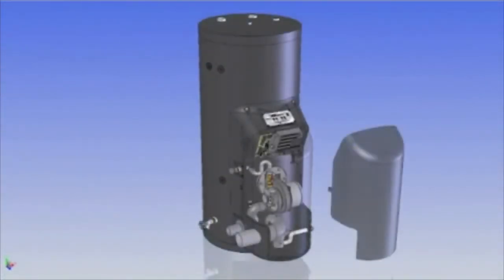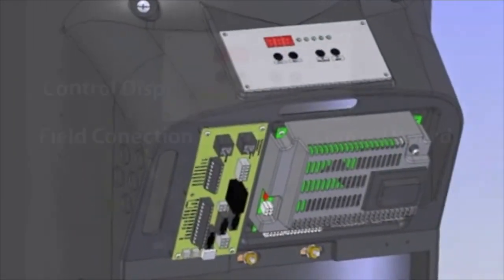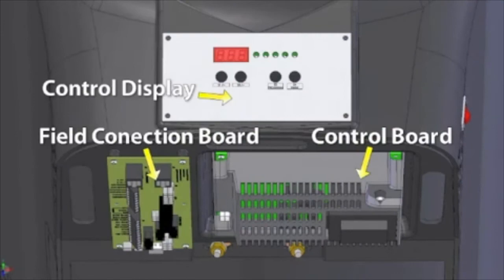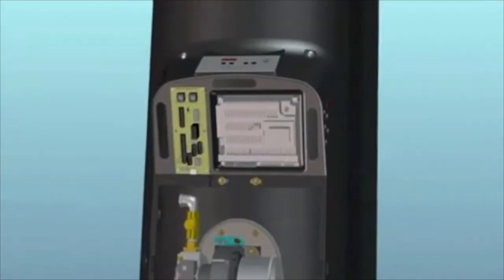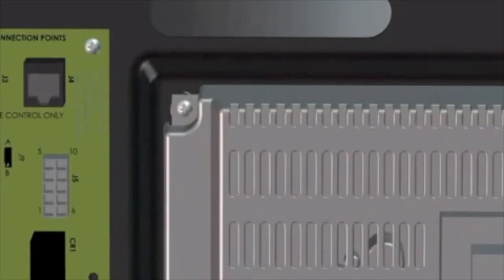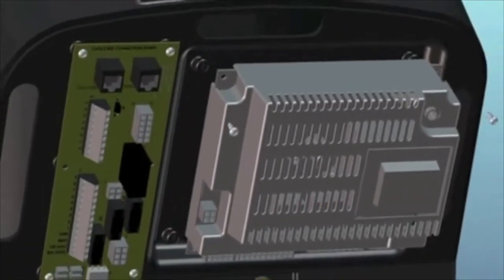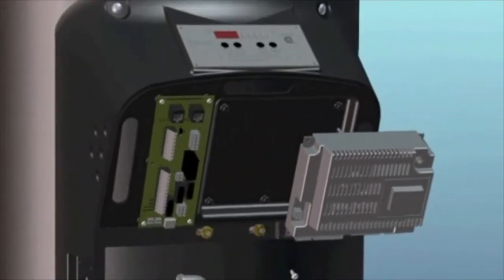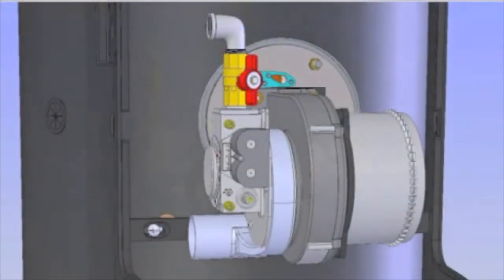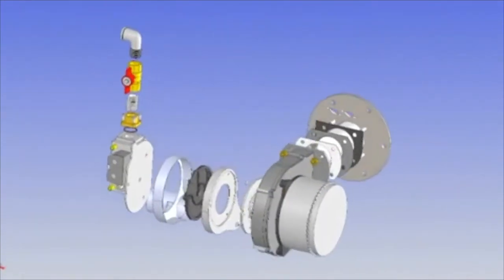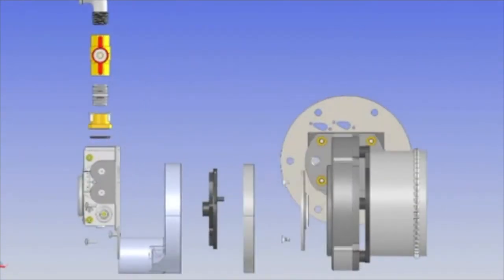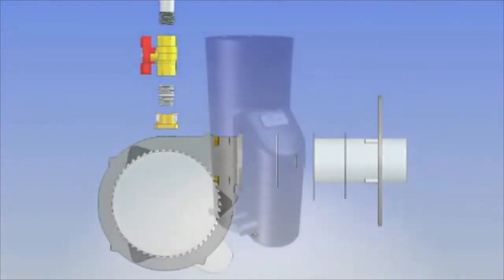Serviceability. Externally located, the Pioneer's entire combustion and control system can be accessed by removing a small light cover. The control board is located at the top of the cabinet and can be easily removed by unclipping 2 harness connectors and 5 small easy access screws. While the gas valve, air venturi, burner assembly is detached by removing 6 easy access screws and one end of the flexible gas line to the valve.